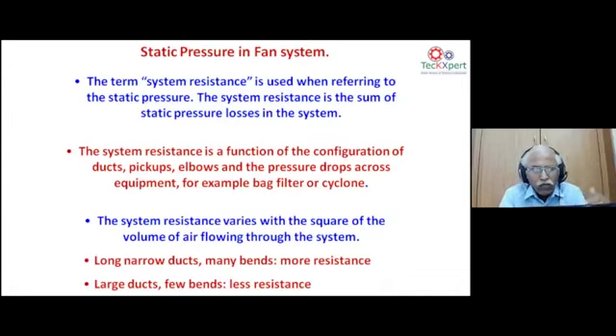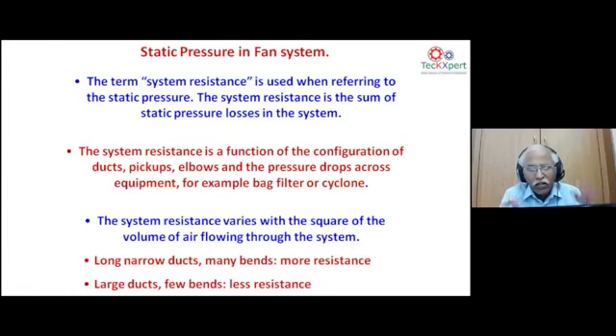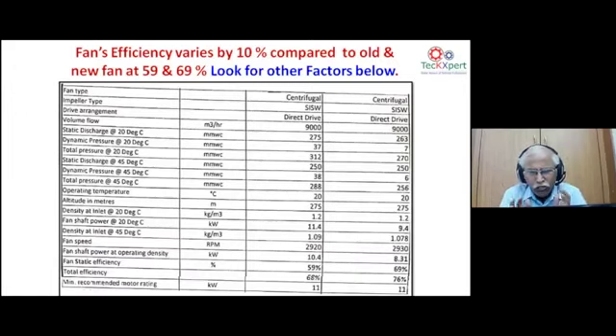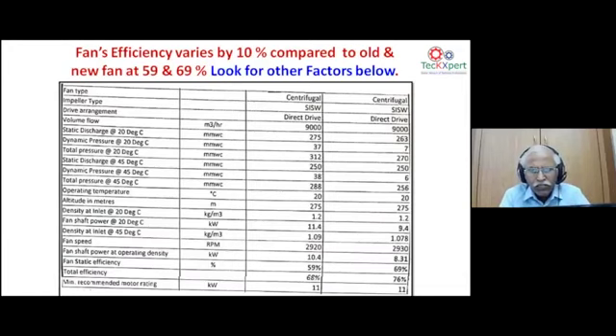System resistance must be maintained to the commissioned norms — what was the static pressure at commissioning vs. after three or five years must be checked routinely. A typical blower spec from a reputed manufacturer shows an existing blower at 59% efficiency and a new improved blower at 69%. The contributing factors to blower efficiency — static discharge at 20°C vs. 45°C — are all itemized in the table, demonstrating how multiple parameters together affect overall blower performance.